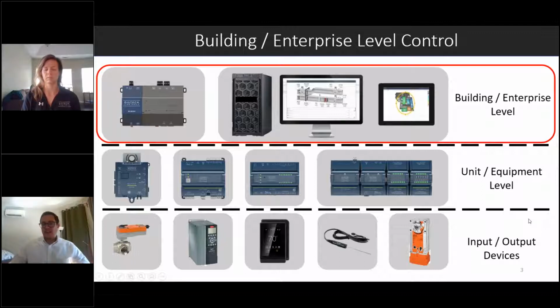All those devices, we said, are wired back to unit level controllers. So every single piece of equipment has its own unit level controller, and its associated sensors are wired back to that. So something like a VAV box, its damper actuator, its space temperature sensor, its airflow, all that are directly housed at that individual unit, wired to that unit. That allows for it to maintain all the safeties as needed for that piece of equipment and also have operation in case it loses communication with the rest of the BAS.